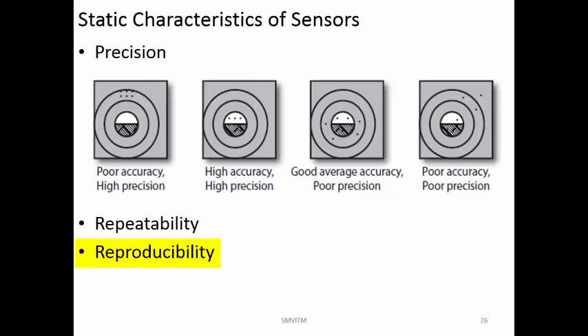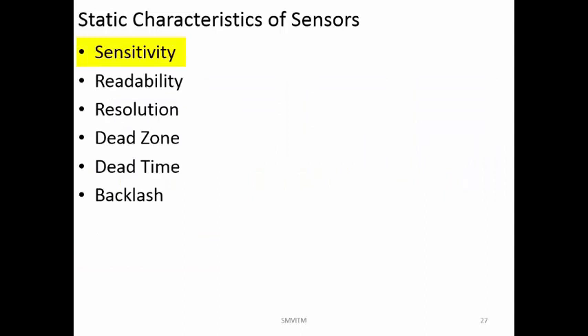So you want to cancel out all the variations that are coming from all these things. So you are using a parameter called reproducibility. The next parameter is the sensitivity. Now what is the sensitivity? Sensitivity is actually measured by the ratio of the change in output to the change in input. So you are making a small change in the input value, and correspondingly, how much is the output changing?